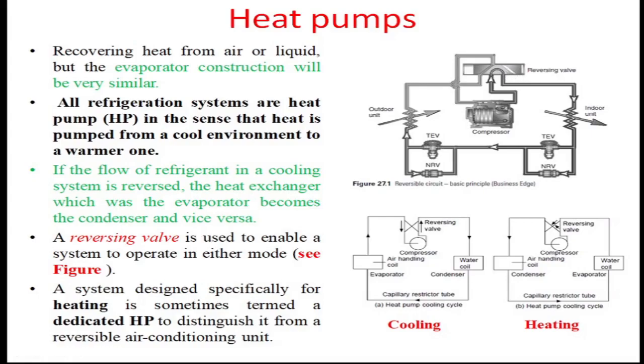The reversing valve has three lines at the bottom, one line at the top, and in between this valve structure, we have three different connections: two slanting slots and a U-bend. When this reversing valve is in the shown position, the compressor discharge side is connected at the top. The block can move to switch flow direction — when it shifts, the U-bend connects two lines and the suction and discharge sides switch their direction of flow.